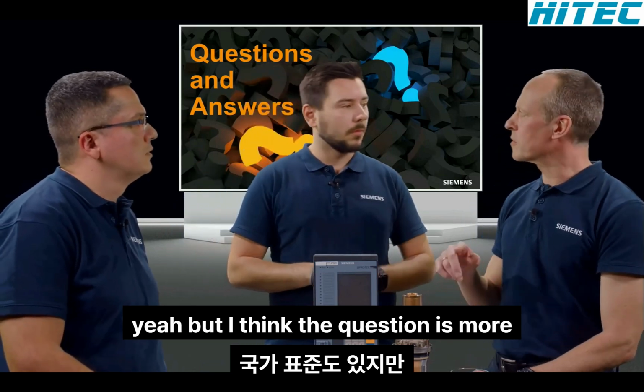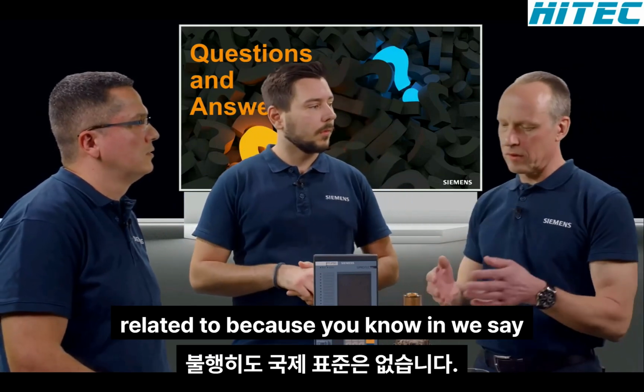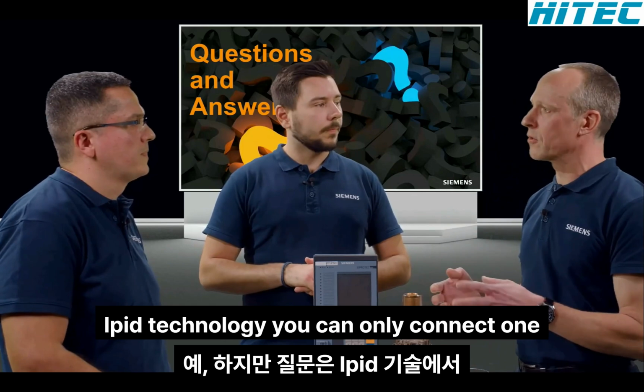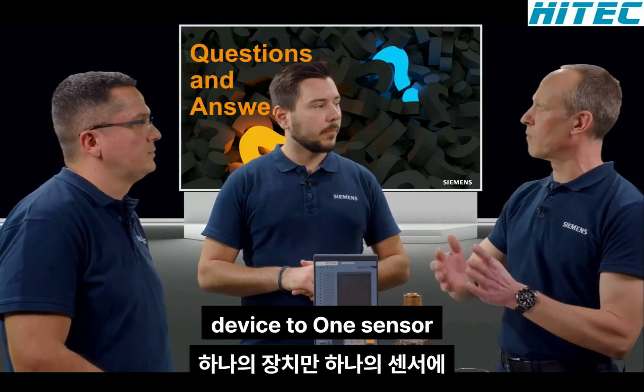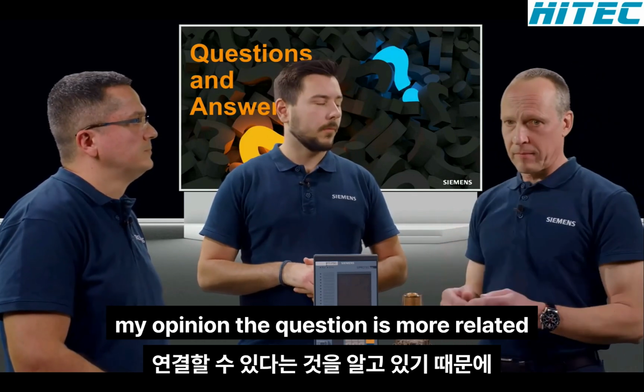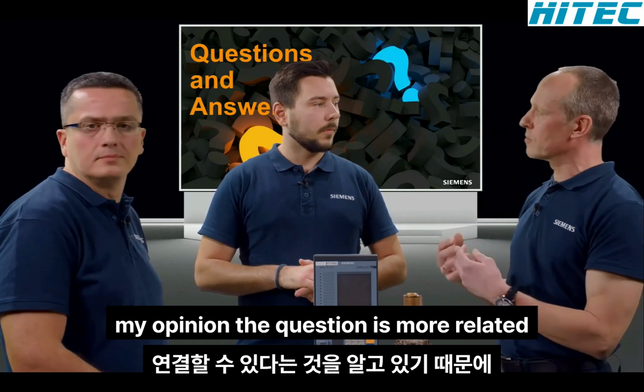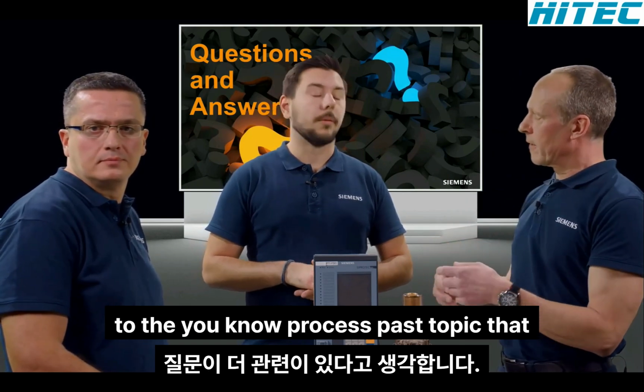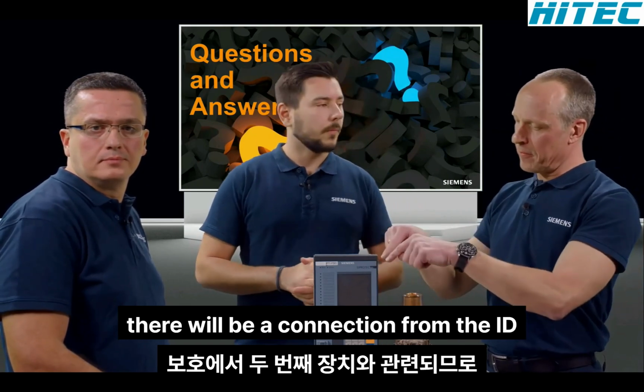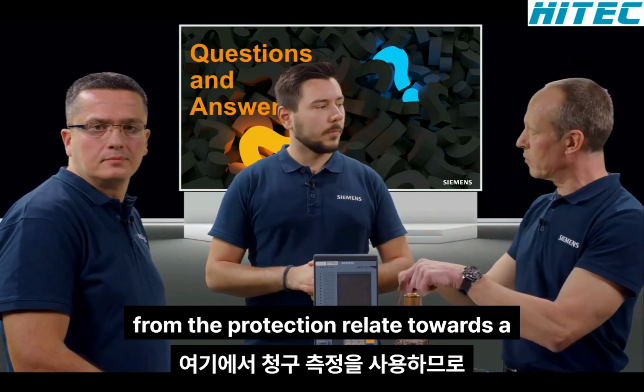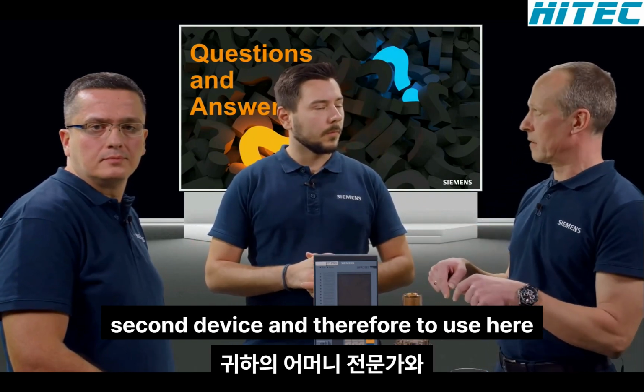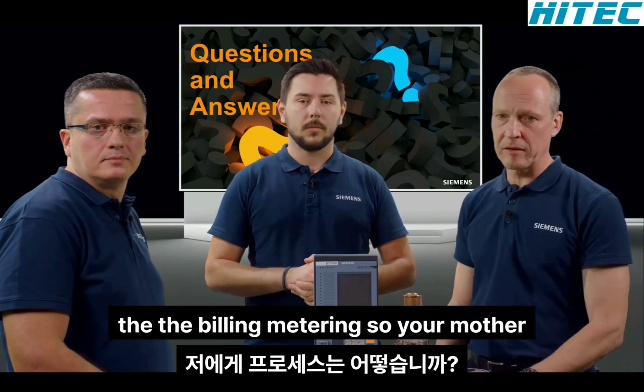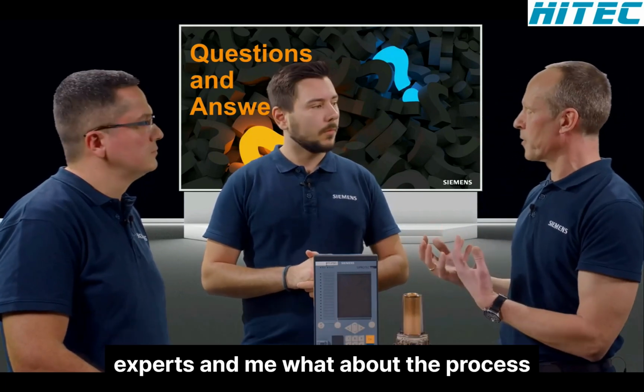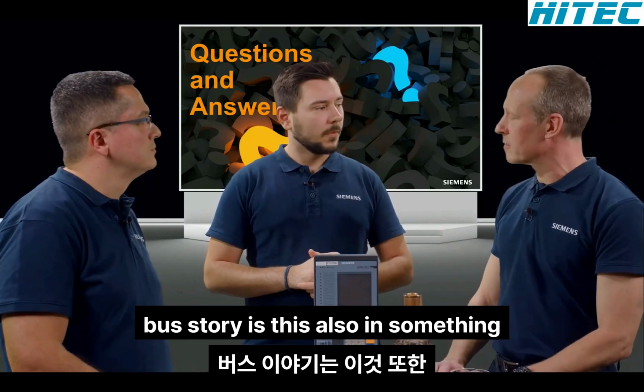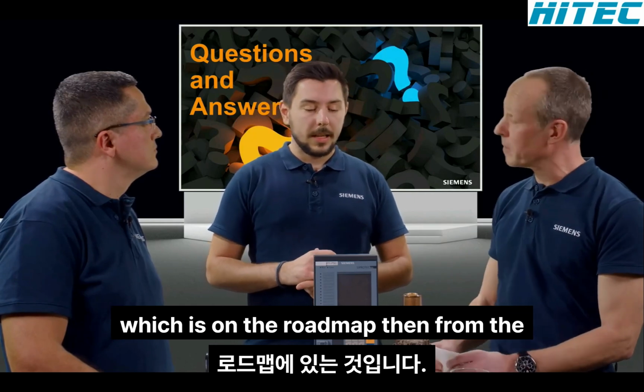Yeah, but I think the question is more related to, because with the LPIT technology you can only connect one device to one sensor. In my opinion, the question is more related to the process bus topic, that there will be a connection from the IED, from the protection relay, towards a second device, and therefore to use it for billing metering. So you're more the experts than me. What about the process bus story? Is this also something which is on the roadmap for the future?